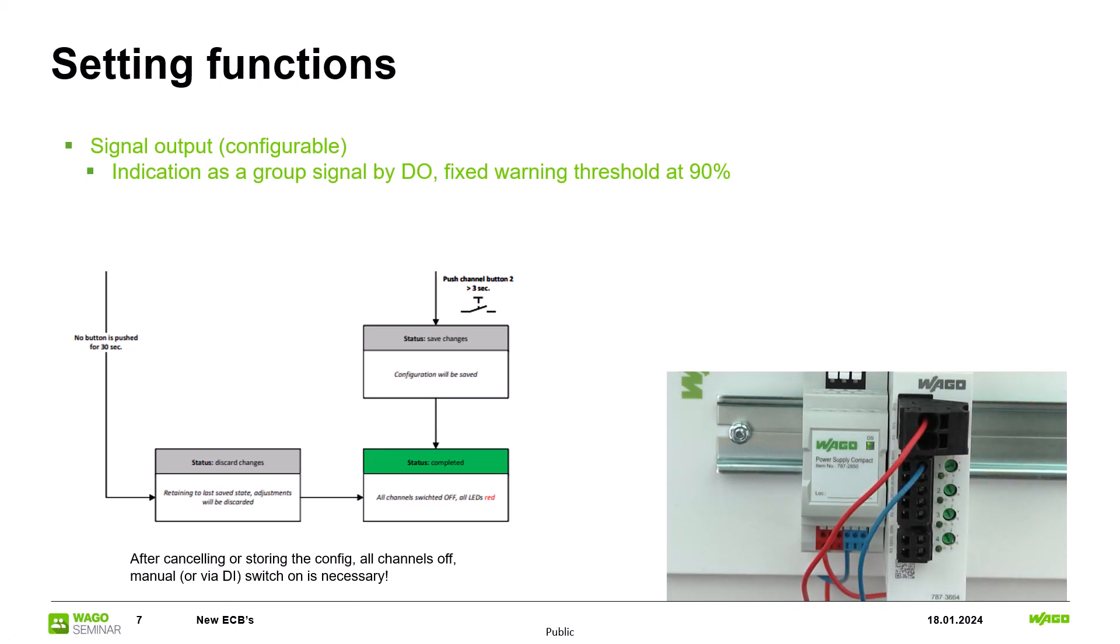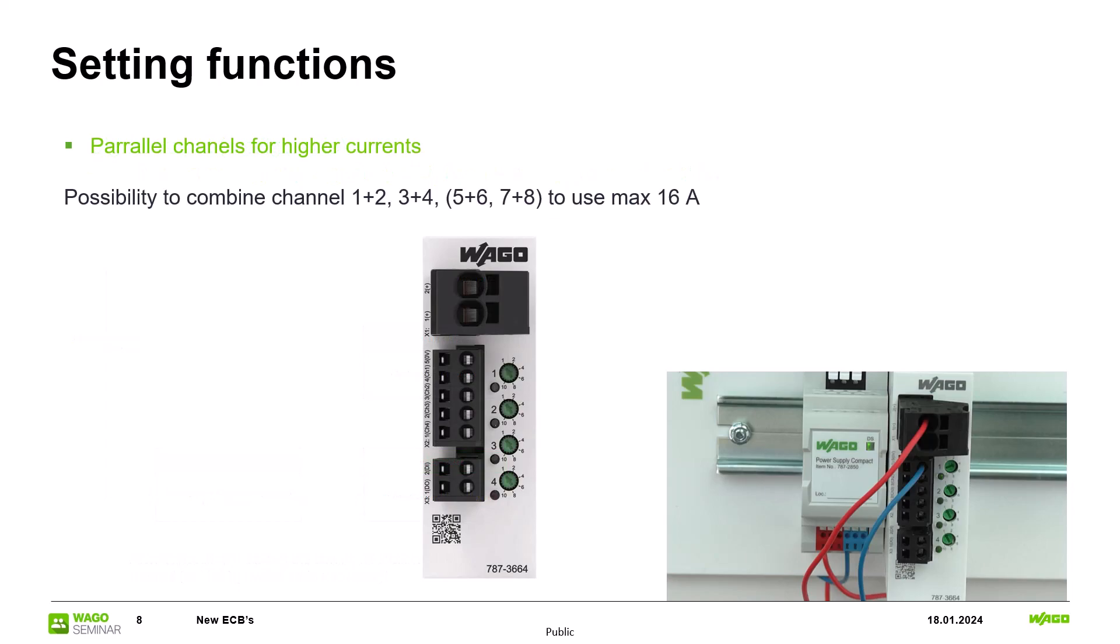Another function is to set two channels in parallel mode to increase the trip current to 16A. With a 4 channel fuse channel 1 and 2 as well as 3 and 4 can be connected together. If you have an 8 channel ECB you can also use 5 and 6 as well as 7 and 8 together.